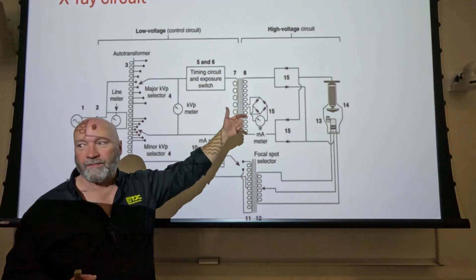Remembering back from last semester, all the controls that we can put into the system, we want on the primary side of the high voltage transformer because it works off low voltage and it's safer. The one exception to that is our mA meter.